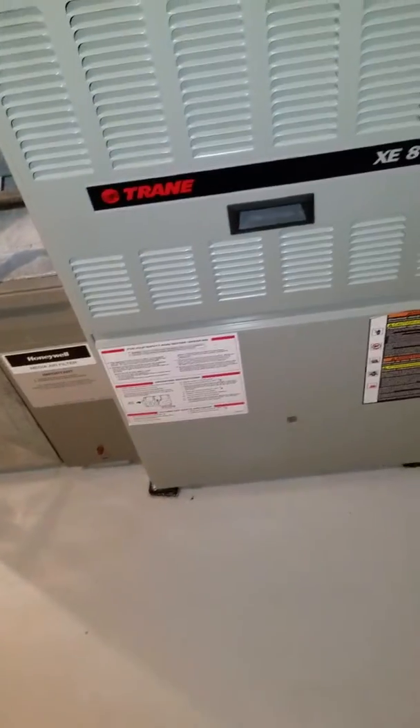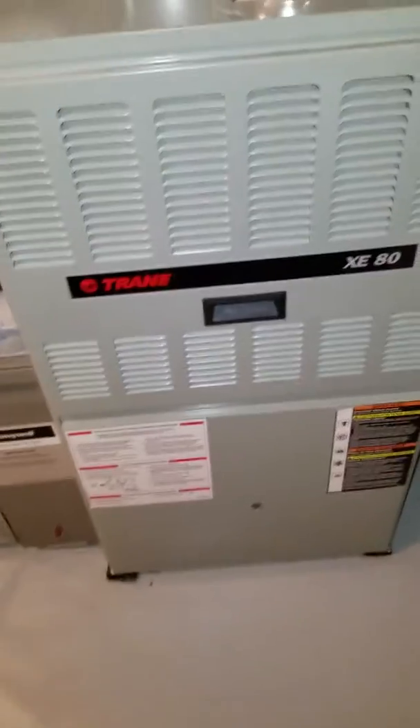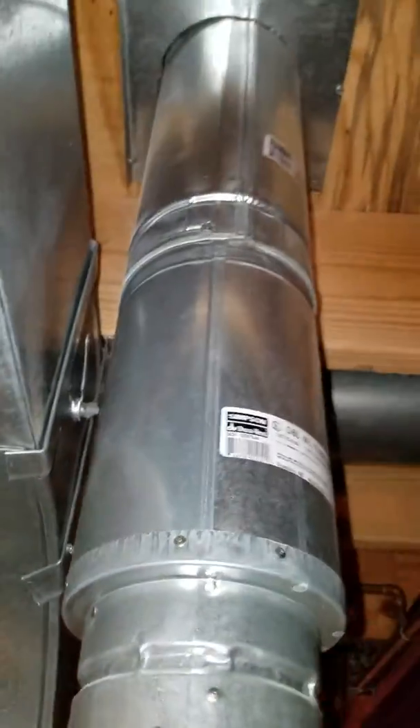You're looking at a Trane 120,000 BTU XE-80 furnace with a 4-inch flue that runs up and ties in with the water heater via a double-walled flue. There's a 3/4-inch gas line that comes in on the left, along with the electric that comes in on the left — here's your gas line.